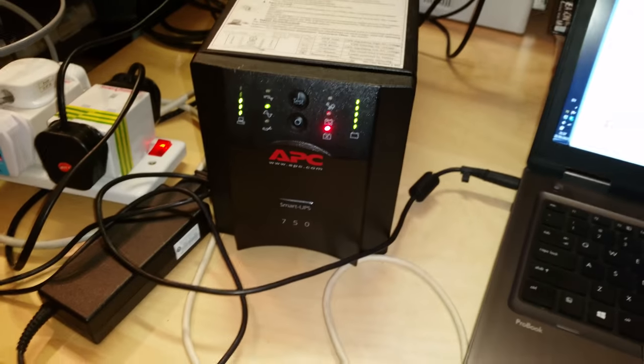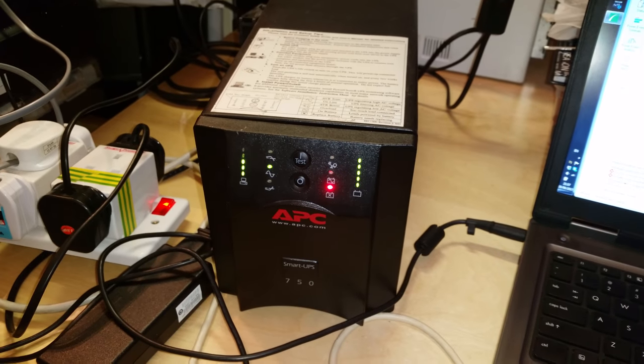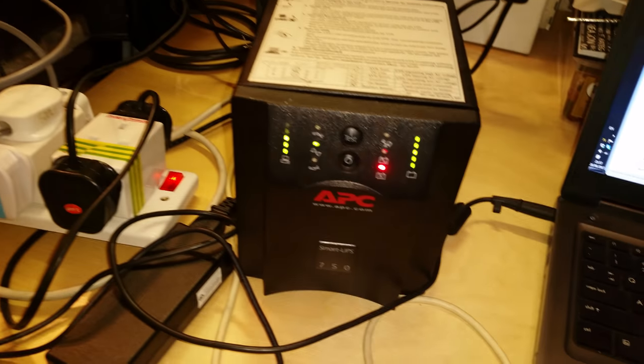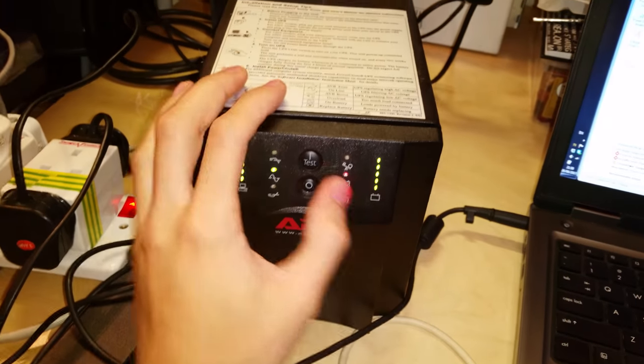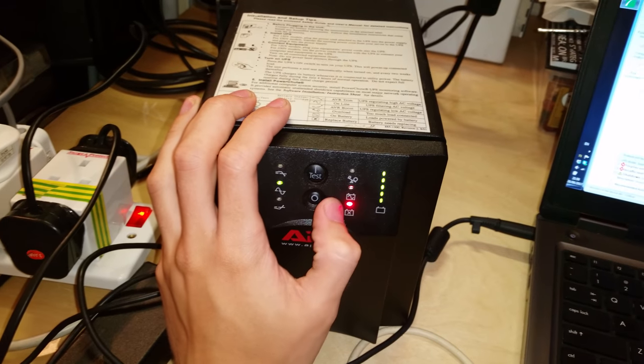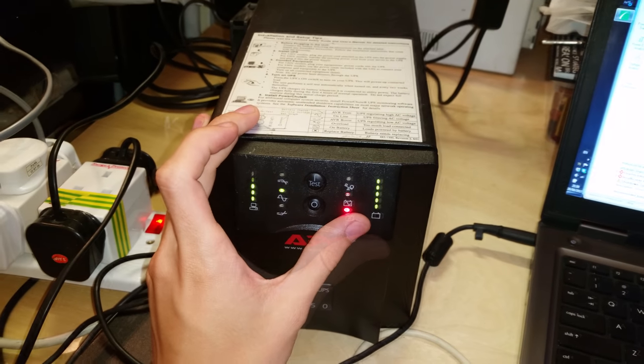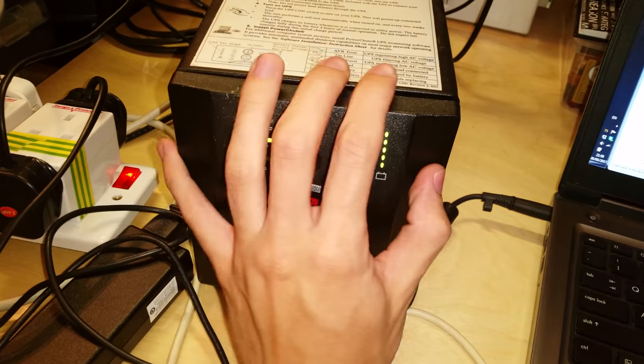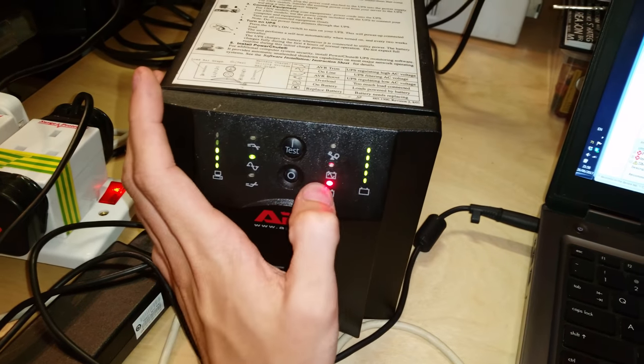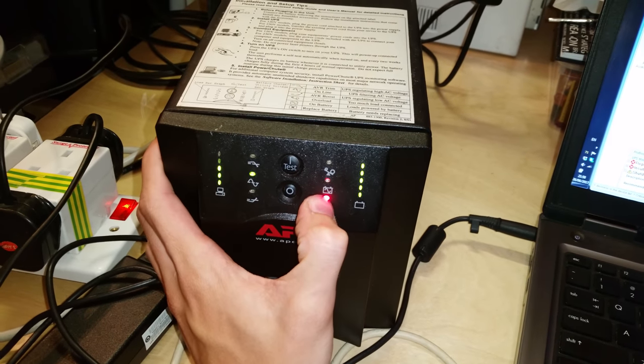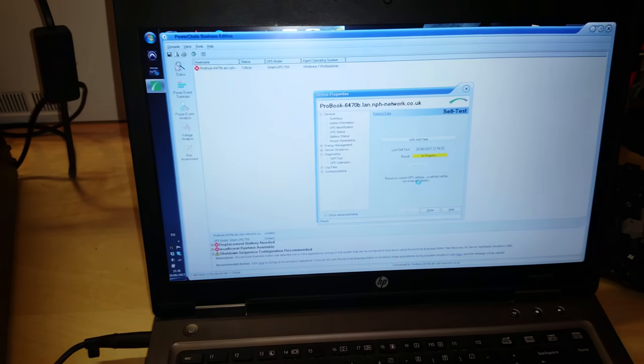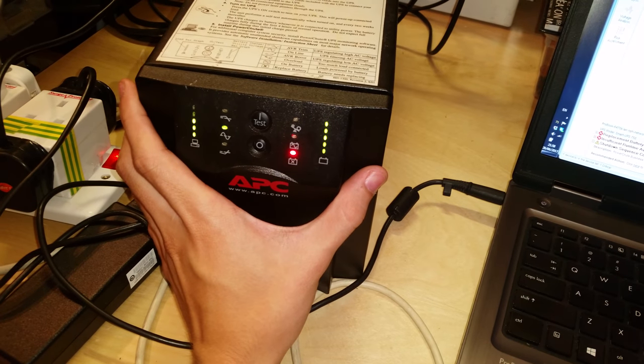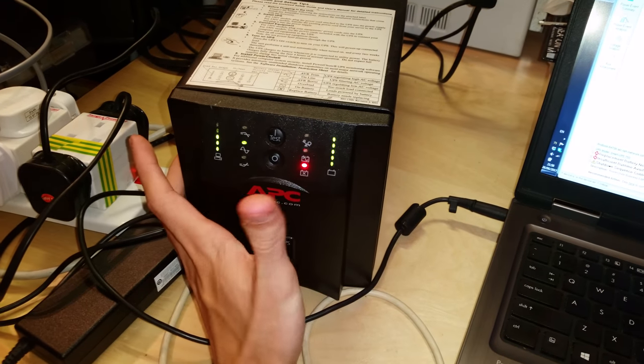Okay, so I did let it do a self test. I was just messing around within the software here. It's fully charged now again, but you can see during the self test it's just completely failed. As soon as it's kicked in to try and run on battery power, this light's come on and it's just been like nope, started beeping and it's just cancelled the test. So even though these batteries are charged up again and going, they will not run in this UPS sufficiently unfortunately.